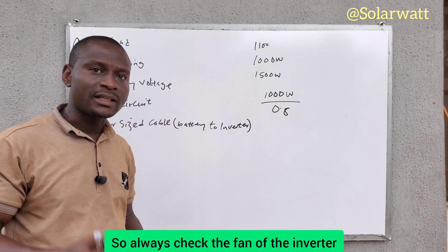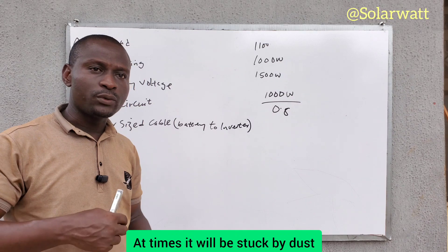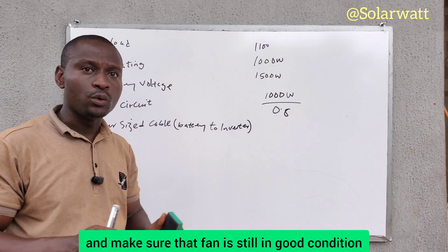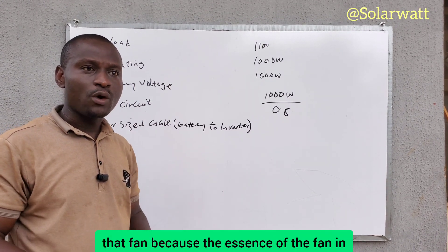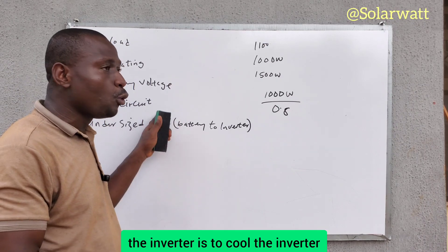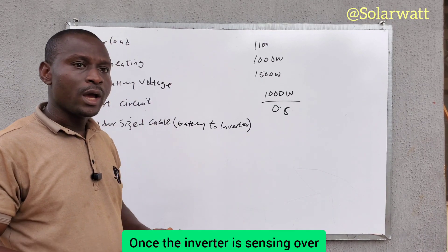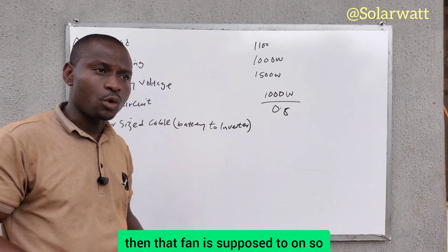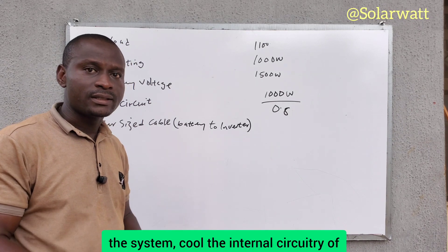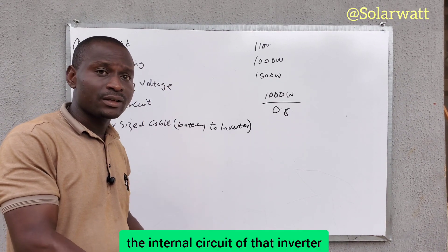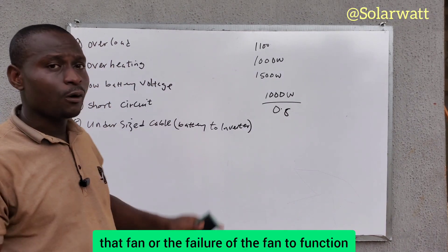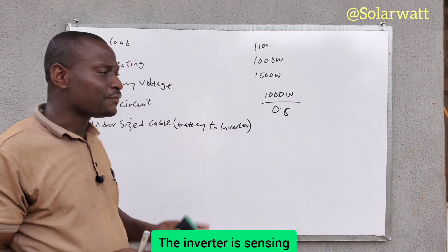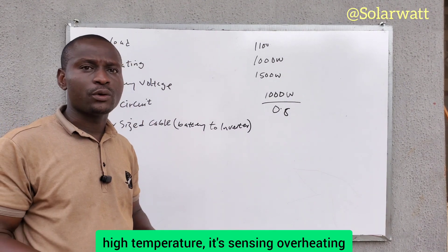Always check the fan of the inverter to see whether it is still working. At times it will be stuck by dust — you need to dust the fan and make sure it is in good condition. If it is not working, you'll need to replace it, because the purpose of the fan is to cool the inverter. Once the inverter senses high temperature overheating, the fan is supposed to come on to cool the internal circuitry. The absence or failure of the fan will make the inverter start shutting down when it senses high temperature.